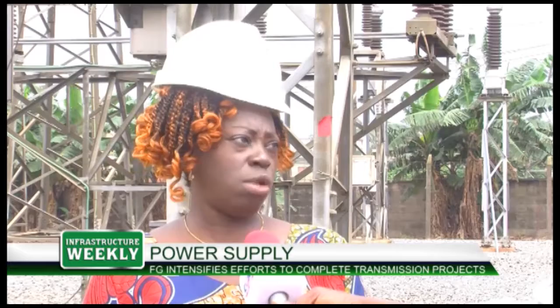Initially we used to have 2 by 60 MVA transformers in the station, and a 100 MVA transformer, but later another was added, making it 3 by 60 MVA transformers. Most of our feeders initially were complaining, and we used to do a lot of load shedding to maintain stability in the system. But now, with the help of the new 60 MVA transformer added to the station, we are no longer doing load shedding.